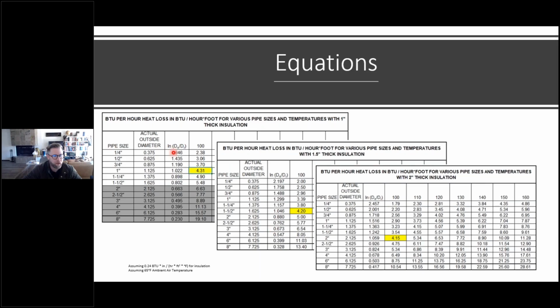Now, one thing I wanted to point out, I mentioned before about the Uniform Plumbing Code, for 100 degrees, 1 inch thick insulation, 1.5 inch thick insulation, and 2 inch thick insulation for the corresponding pipe size. Remember, I indicated that the heat transfer rate would be almost identical, and that's what we see here. So you end up with right around somewhere in the range of less than 4.5 BTU per hour per lineal foot when you match pipe size in those cases. And you would expect to see that as it continues to increase in size.